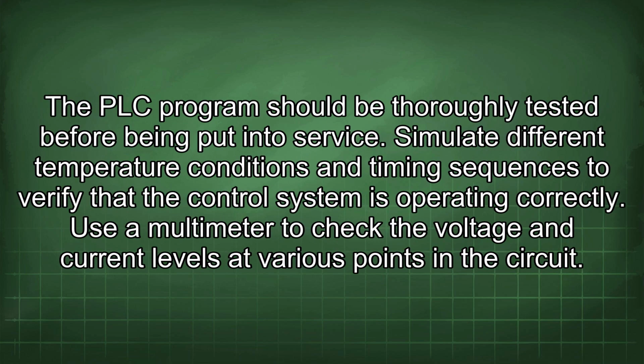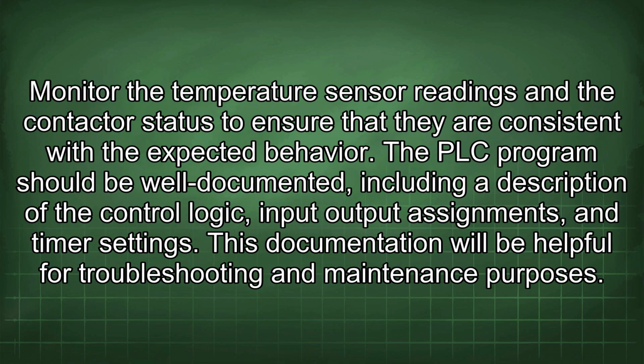The PLC program should be thoroughly tested before being put into service. Simulate different temperature conditions and timing sequences to verify that the control system is operating correctly. Use a multimeter to check the voltage and current levels at various points in the circuit. Monitor the temperature sensor readings and the contactor status to ensure that they are consistent with the expected behavior.